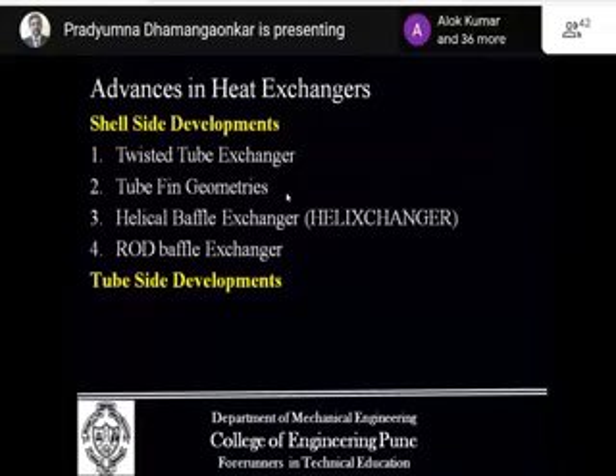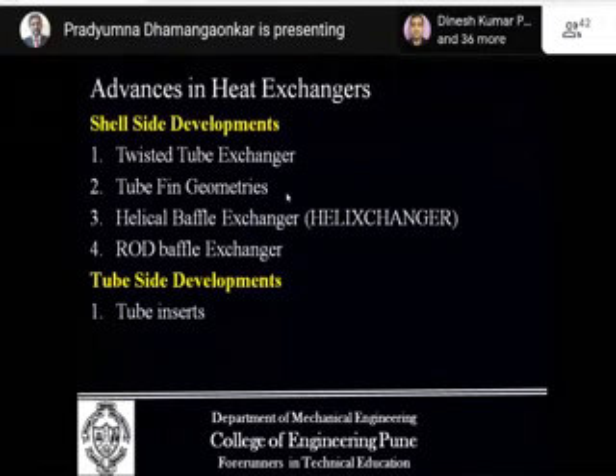One is the twisted tube heat exchanger. Second is the tube fin geometries; different tube fin geometries are used. Third is the helical baffle heat exchanger, called the helixchanger. And fourth is the rod baffle heat exchanger. On the tube side, there are tube inserts, and even different plates are also used for improving the flow pattern and the flow velocity or the flow configuration.